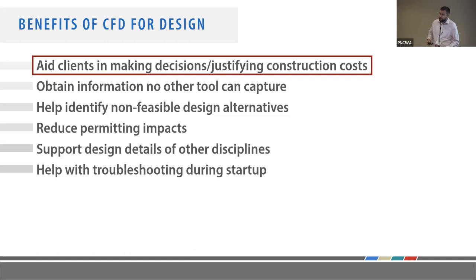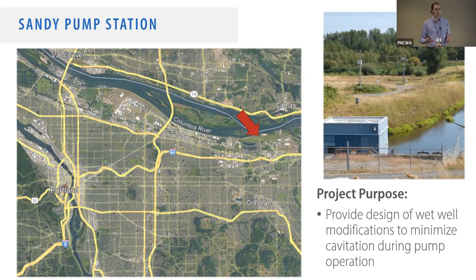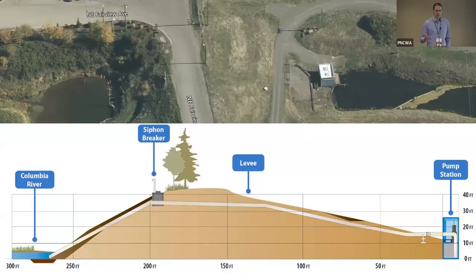To start, we'll discuss how we used CFD to help justify construction costs for a client. This is the Sandy Pump Station in northeast Portland — a flood management and flood control pump station. The purpose was to look at providing modifications to the wet well, which was built back in the 1940s. The pumps have been upgraded and upsized over time, but the wet well stayed the same shape. It no longer aligns with Hydraulic Institute standards, and operators noted sounds like cavitation, raising concerns about pump longevity and operation.